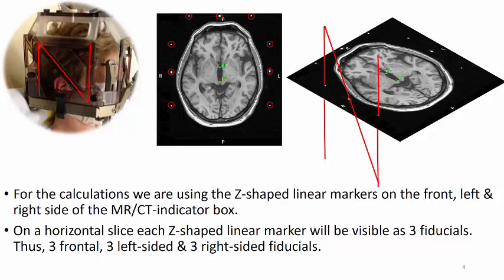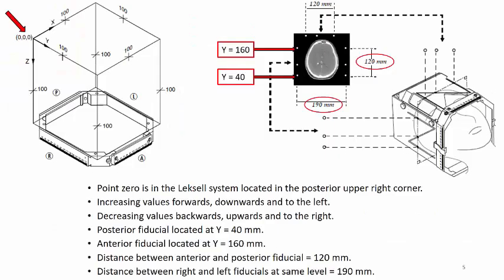On a horizontal slice, each Z-shaped linear marker will be visible as three fiducials. Thus, three frontal, three left-sided and three right-sided fiducials. Point zero is in the Leksell system located in the posterior upper right corner and we have increasing values forwards, downwards and to the left.